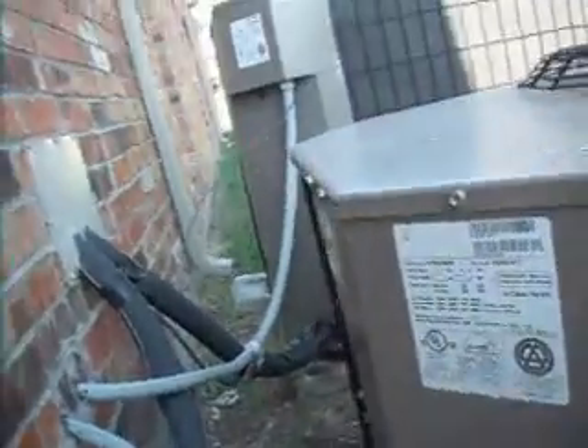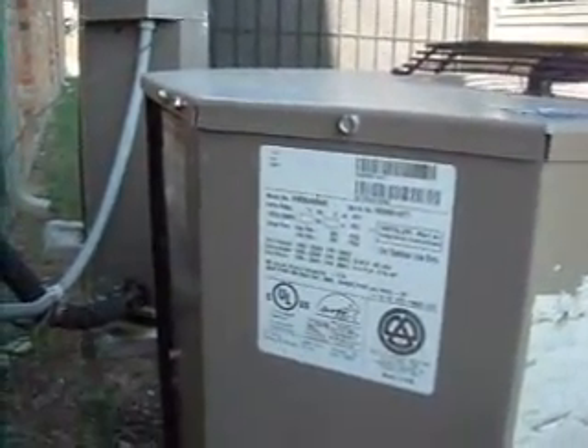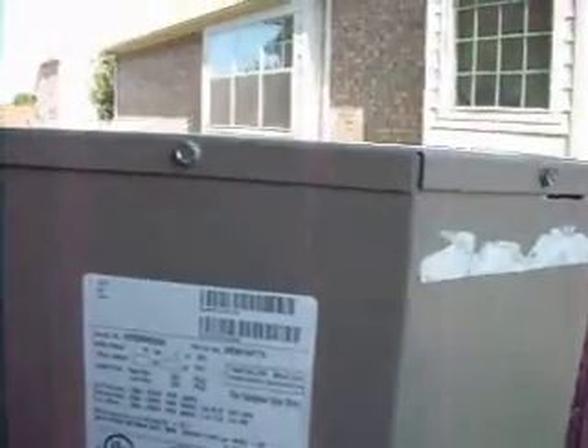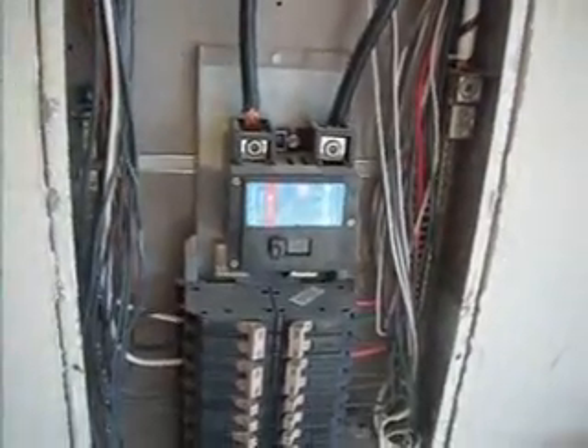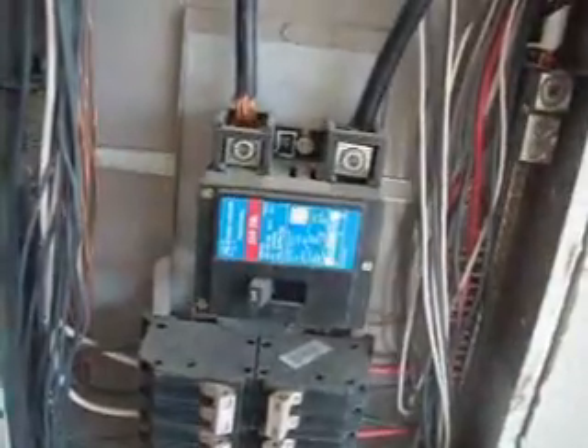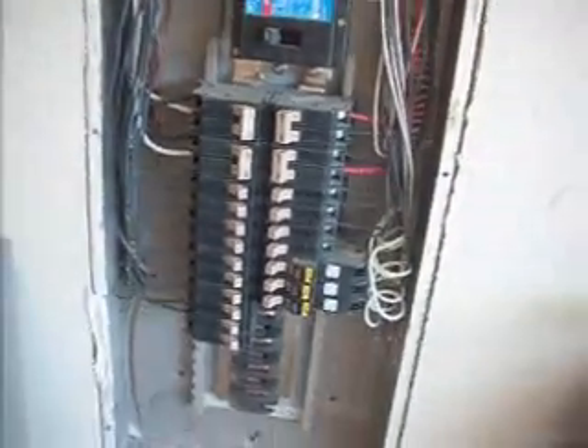Here's the compressors, and one has a 20 and the other has a 50. This is 20 amp. It's there. And this one calls for a 50 amp. It's correct. We have a 240, 120 supply, 200 amp breaker.